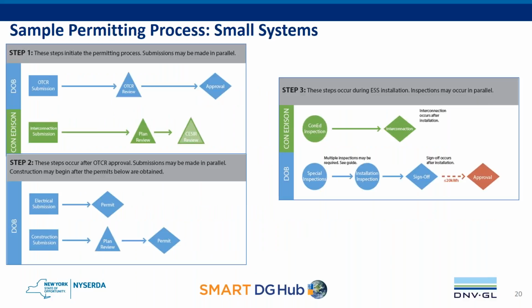So I'm just going to go through this really quickly, but we have 2 slides here, one for small systems and one for medium and large systems. As I mentioned earlier, this is really a multi-organizational process. So in all cases, the utility, the Department of Buildings, and the fire department move forward in concert on installations. Starting in step 1, submission of documentation and approval moves forward.